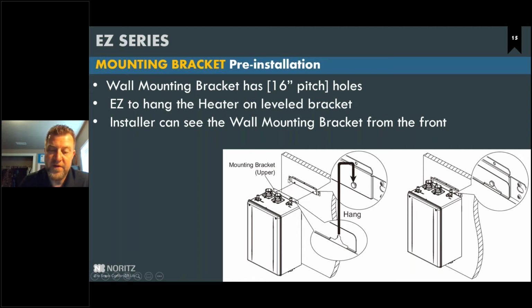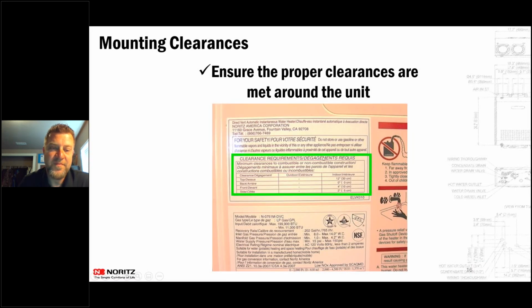So we actually have a unit where the bracket shows you the in and the out on the top. So if you are running PVC to that, it'll actually line it straight up, and it does have some fudgeability where you can move the unit to the left, move the unit to the right to line up piping and different things like that. So they've really come a long way on the mounting options on the top of those units.